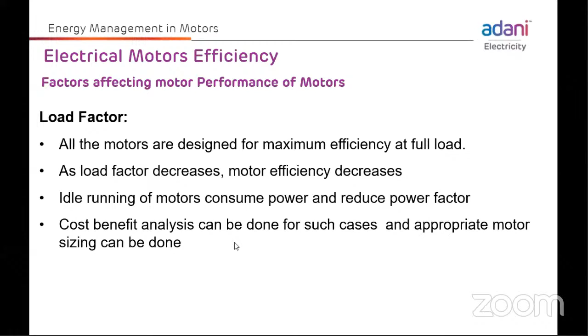Then rewinding is also one of the factors. Many times we do rewinding of motors from local or non-standard vendors. What they do is heat up the entire core to remove the winding, using a crude method. Due to this heating, there is insulation damage and eddy current loss increases, which also decreases the efficiency of the rewound motor. So rewinding of a motor should be ensured properly - proper materials and standard methods should be used. Otherwise it will reduce the efficiency by more than 1 to 2%.